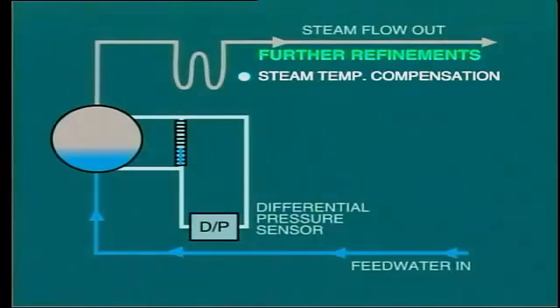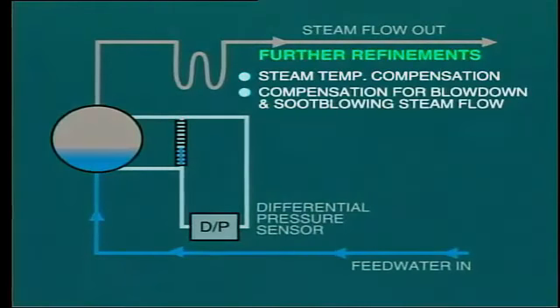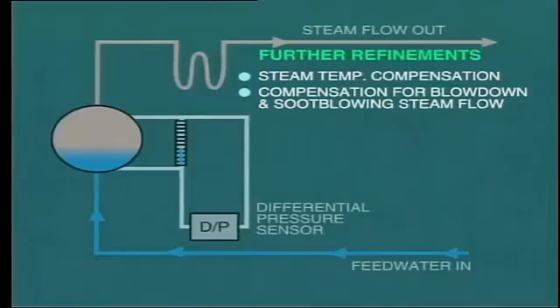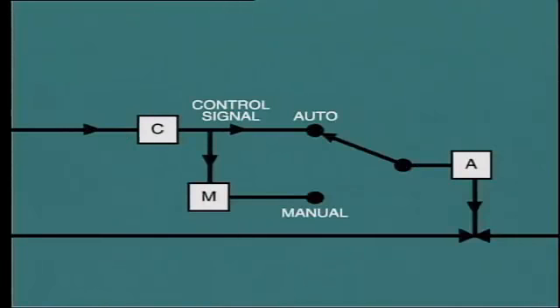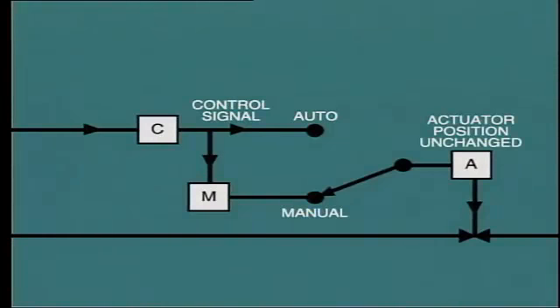Yet further refinements may be made to the water level control system, such as steam temperature compensation to provide more accurate measurement of steam flow, and compensation for blowdown and soot blowing steam flow when comparing output steam flow to input feed water flow. You must make sure to thoroughly learn the automatic control systems installed on your boilers. One very important feature of any control system is that it must provide smooth transfer from automatic to manual operation and vice versa. In most systems this is achieved by making the alternative selection continuously follow the actual output signals to the actuators, so any switching keeps the actuator in the same position until further change is made.